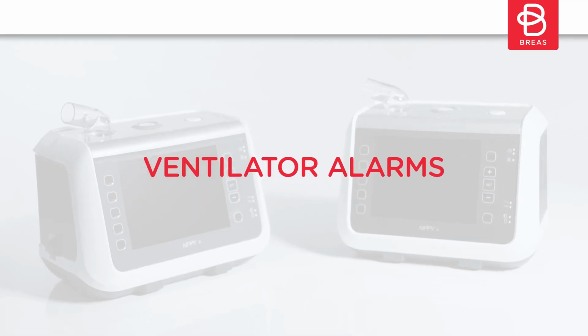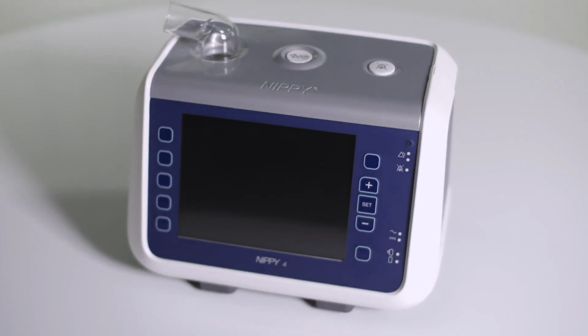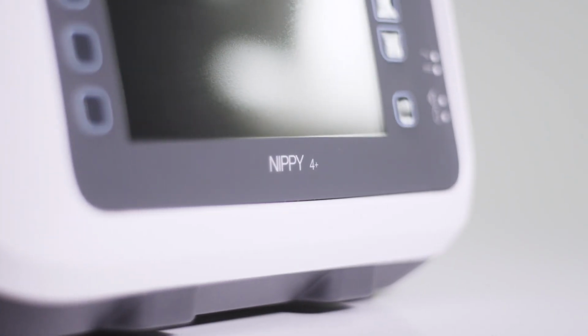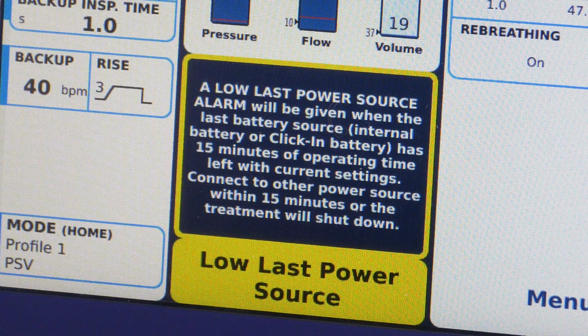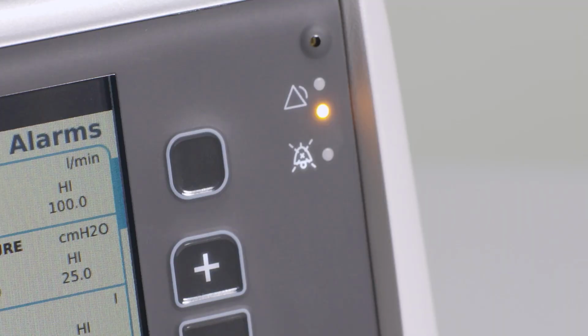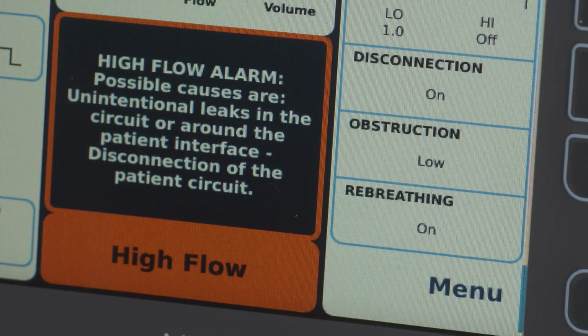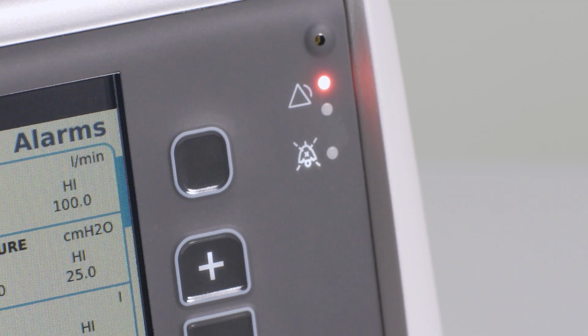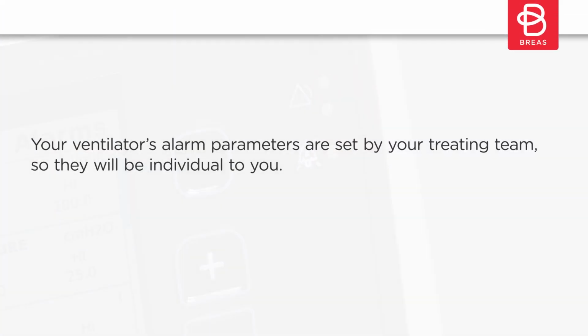Ventilator alarms. There are two types of alarms on the Nippy 4 and 4+. There are medium priority alarms, which will be identified by a yellow message on screen and a flashing yellow LED light in the top right corner with an audible alarm, and high priority alarms, which is signalled by a red message on screen and a red LED light in the top right corner, and a more continuous audible alarm. Your ventilator's alarm parameters are set by your treating team, so they will be individual to you.